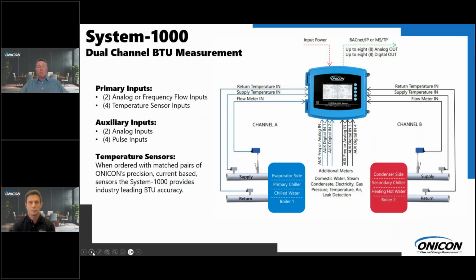One of the great things about the System-1000 is it's a true dual channel BTU measurement system. As you can see on the diagram on the right, we consider the System-1000 to be split in half with 2 fully independent channels. On channel A on the left, you can have a full independent BTU measurement of your evaporator side, of your primary chiller. You could have a boiler hooked up to that. And on the right side on channel B, you can have your condenser side, your cooling tower, a secondary chiller if you're staging chillers. You can do heating, hot water, a boiler. It doesn't matter. Both of these channels are fully independent in how they calculate and measure BTUs.